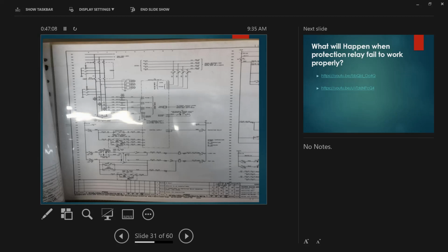That supervision relay you're talking about, is that an old thing now? Inter-trip? No, it's still applicable. Is that one relay sending a signal to the supervision relay and that trips the breaker? It monitors the coil. It is maintained by the trip circuit supervision, so it also monitors the coil. If your breaker is open, it's trying to monitor the closing coil. If the closing coil is healthy, there is some kind of continuity, the voltage drops anyway, so it will allow you to close the breaker. If that one is not healthy, or for some reason you pull out that specific terminal monitoring that closing coil, it won't allow you to close the breaker.